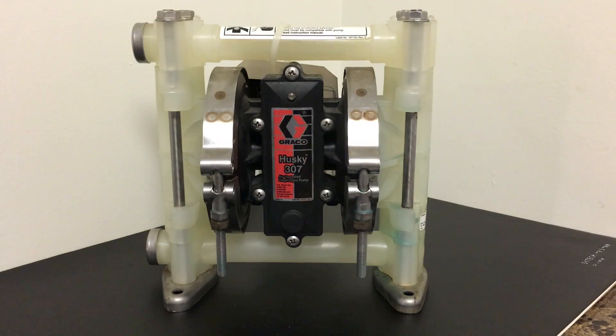Once you diagnose all that and see everything is working correctly, then start looking at the pump side of the issue. So there's really only two main issues that this pump could have: one being the diaphragm, and the second being the air valve which is directly in the center.